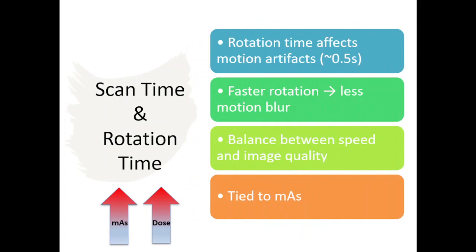Rotation time plays a crucial role in reducing motion artifacts. Faster rotation times minimize blurring in moving structures like the heart, but may require trade-offs in image quality. A diagnostic CT scanner typically completes one full rotation in 0.5 seconds, allowing for rapid imaging, and state-of-the-art CT scanners can capture the entire heart in a single heartbeat. Radiation oncology CT simulators often use a one-second rotation time, balancing image quality with dose considerations.